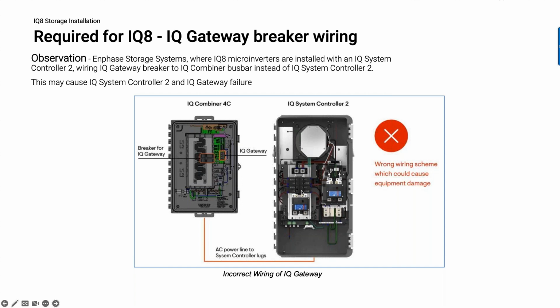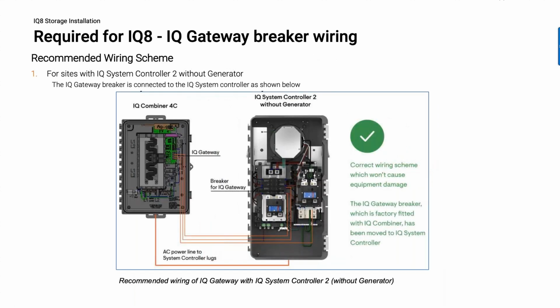So that is one example of why it's important to move this gateway power to here. There's another reason for this, which is that there is actually a power dynamic where if the gateway is not powered off of this bus, it actually creates an electrical dynamic in the system controller that could actually damage the system controller. All right, so two reasons why this gateway needs to be powered off of the system controller bus. How do you do this?